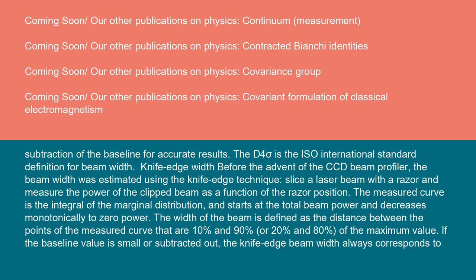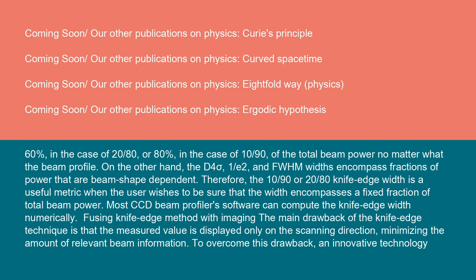Knife edge width: Before the advent of the CCD beam profiler, the beam width was estimated using the knife edge technique. Slice a laser beam with a razor and measure the power of the clipped beam as a function of the razor position. The measured curve is the integral of the marginal distribution and starts at the total beam power and decreases monotonically to zero power. The width of the beam is defined as the distance between the points of the measured curve that are 10% and 90% or 20% and 80% of the maximum value.